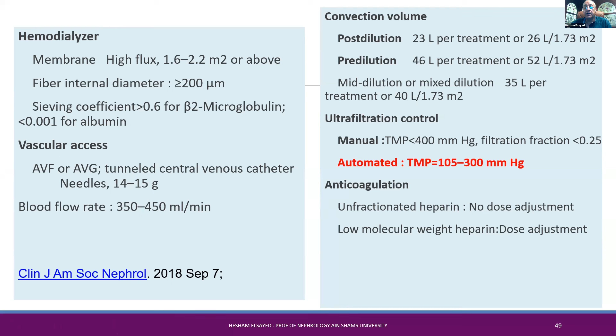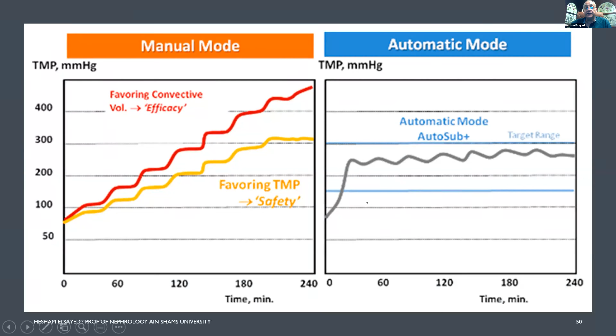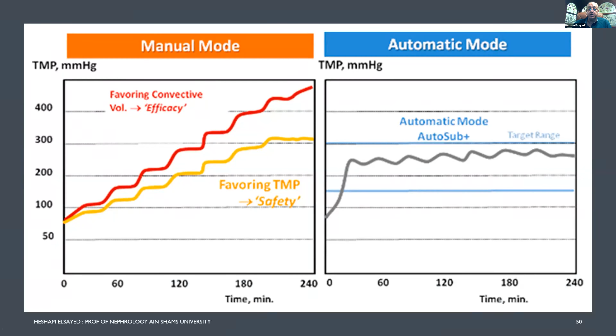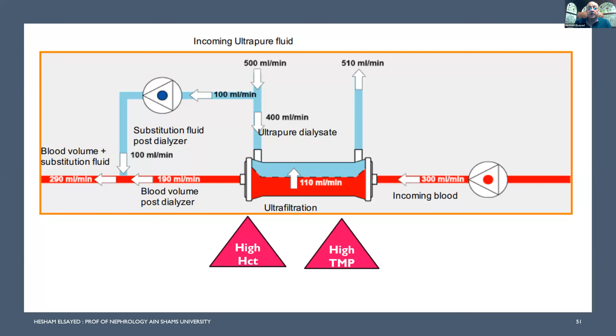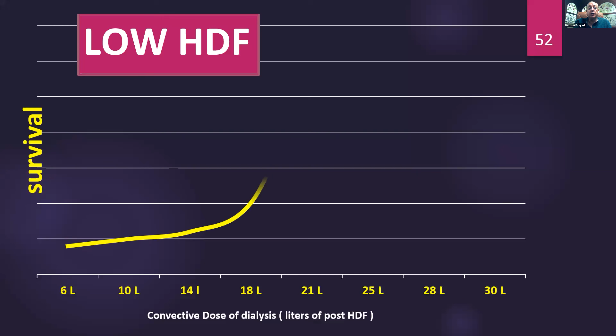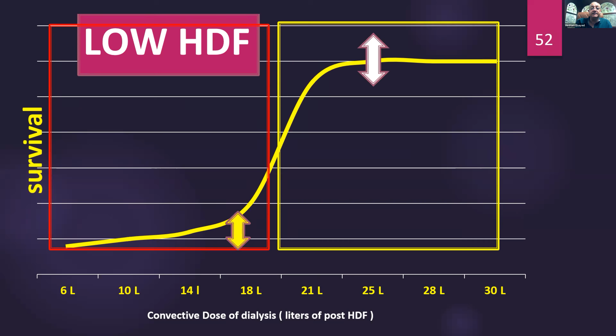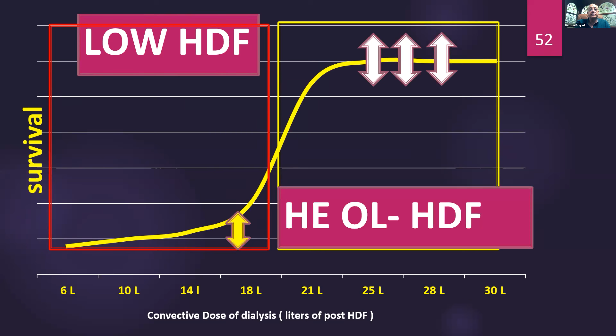The automated part of the hemodialysis machine is important, and you can find here in my last slide, in the manual mode, you can find very high transmembrane pressure, but if you are using the automatic mode, the machine can control by feedback control, and once the transmembrane pressure exceeds 300 mmHg, it stops the ultrafiltration and does on-demand back filtration or intra-circuit injection of saline. I wish that this talk highlights the technique of hemodiafiltration, watching for very high TMP and high hematocrit, and we all know that a high hemodiafiltration dose is related to survival, while a low hemodiafiltration dose is not related to survival and has no benefit, exactly like high flux dialysis. And thank you very much.